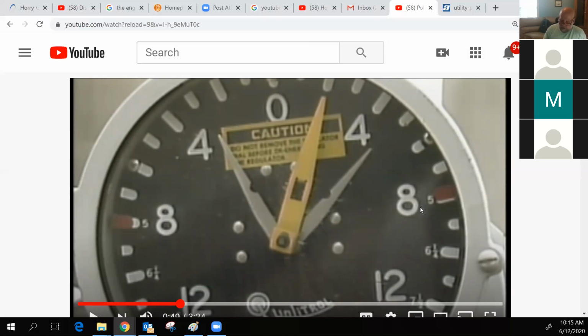There's a control box below this regulator on the pole. It has a reset button inside it. Whenever it came to these regulators, we used to go check them monthly. As part of our checklist, we used to have to go out and check the line capacitor banks and regulators. And once a month, we would note where it was at in the raised position, where it had been on the lower position, and we would reset it, and engineers would get those cards back and they would monitor.